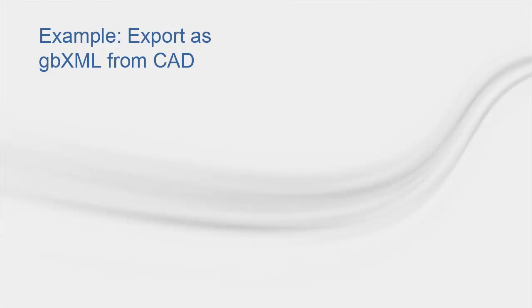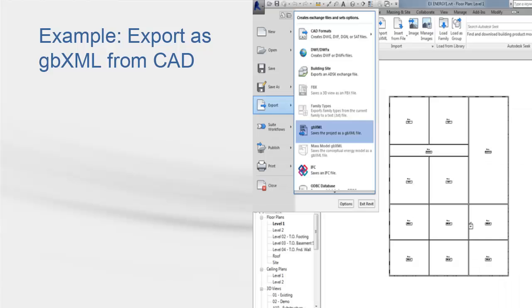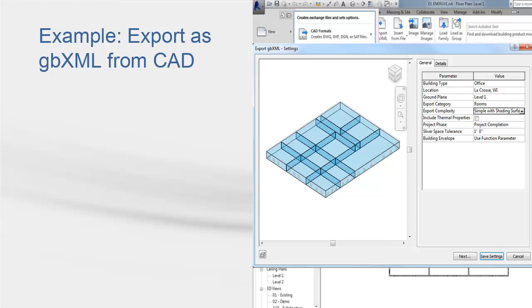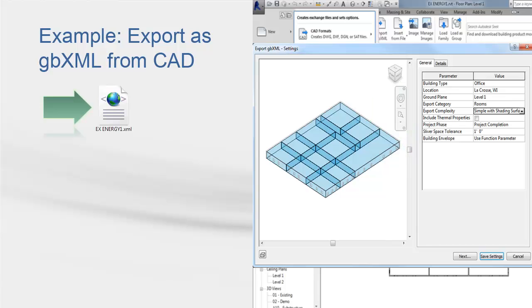Let's look at an example using Autodesk Revit. A building with 12 rooms is created as a CAD drawing. We want to export it as a GBXML file to run the load calculation in Trace 700. To do so, we need to go to the main menu, select the option Export, and click on GBXML. The Export GBXML setting window will allow you to select the building type, location, level of complexity, and category. The exported file will have an extension .xml. Make sure that you save it in the same location that you will save the Trace file and avoid using special characters for the name.